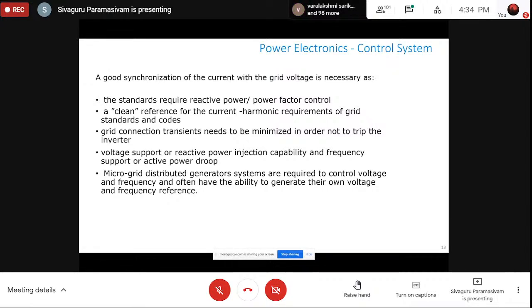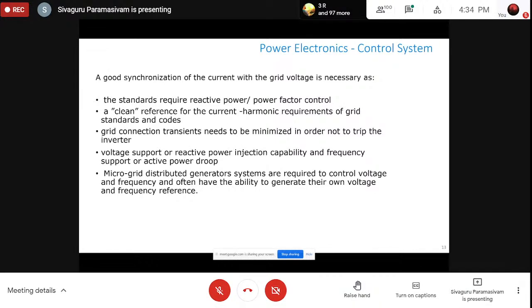Whenever we are connecting a renewable energy asset or a renewable source to the grid or to the load, we need to take care of the reactive power and power factor requirements. We need the power to be clean because we don't want to inject any harmonics. And the grid connection transient. So we will always have the power requirements or the curve going up and down. We will have to minimize those transients.